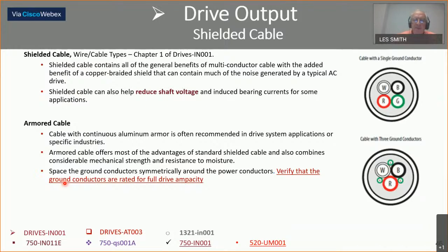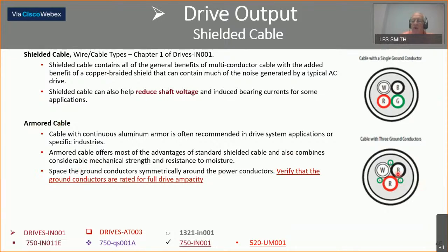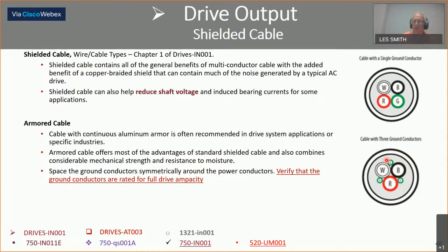Regarding shielded cable: here we see the ground wire going back with phases A, B, and C. We're going to get more ground currents with this arrangement because the conductors are not equally spaced. Whereas with armored cable, the ground wire arrangement and the three leads at 120 degrees apart means there will be cancellation of ground currents and less ground current coming back. However, this only refers to 60 Hz behavior. In a drive running at various frequencies, this layout will still lessen the coupling of noise on the drive wire.